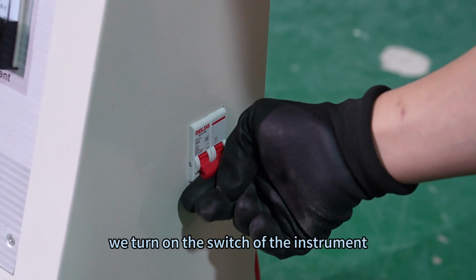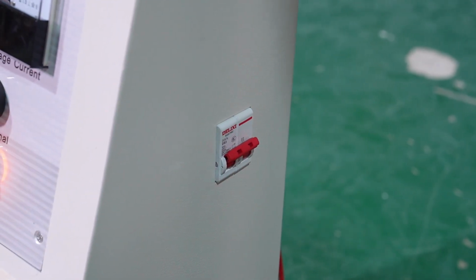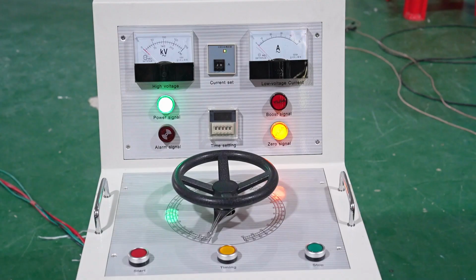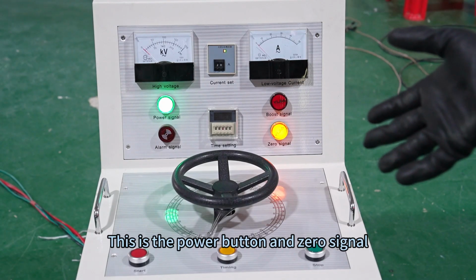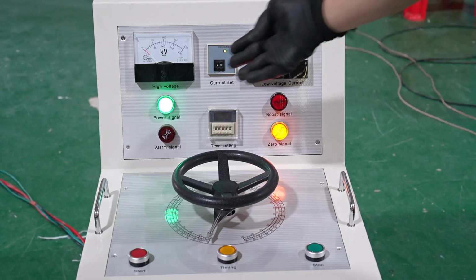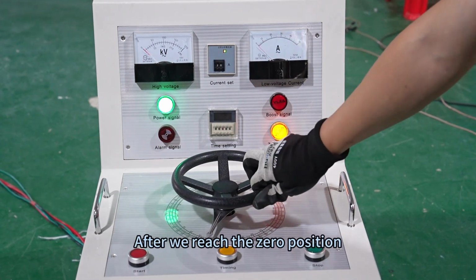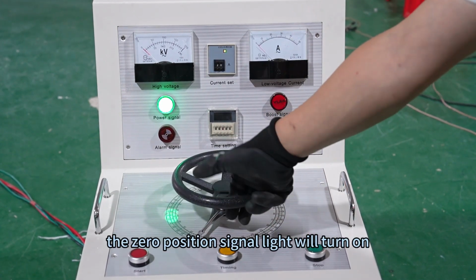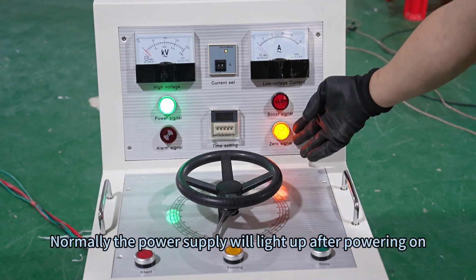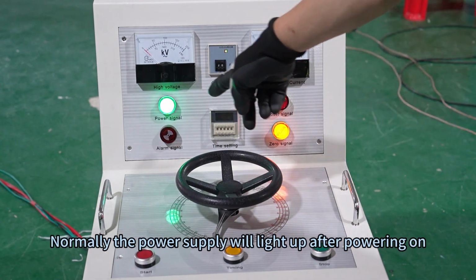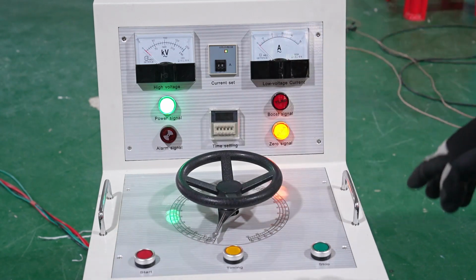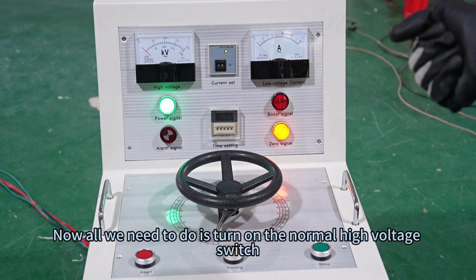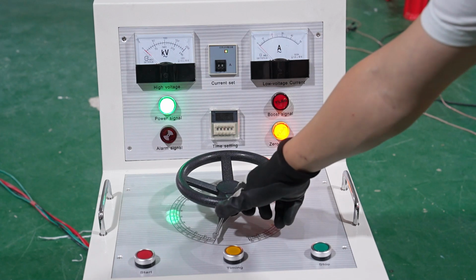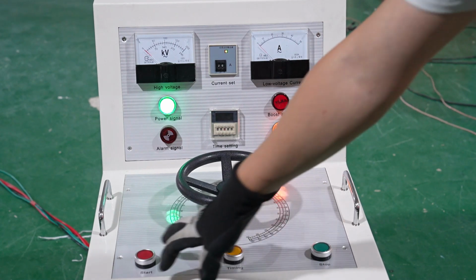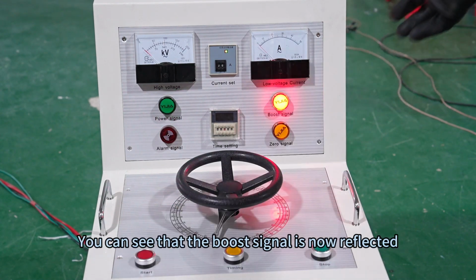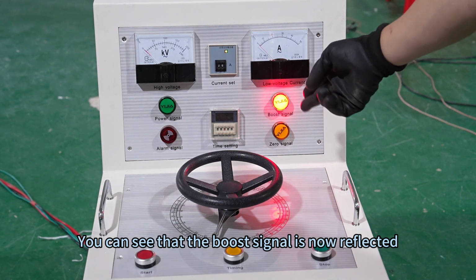During the test, we turn on the switch of the instrument. This is the power button and zero signal. After we reach the zero position, the signal light will turn on. Normally, the power supply will light up after powering on. Now all we need to do is turn on the normal high voltage switch. Then click high voltage pass. You can see that the boost signal is now reflected.